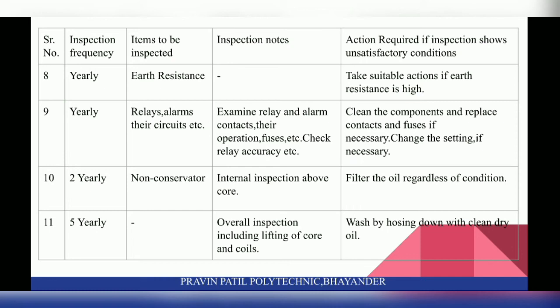On a two-yearly basis, check the non-conservator with internal inspection above the core. Action required: Filter the oil regardless of condition. On a five-yearly basis, perform an overall inspection including lifting of the core and coils, and wash by hosing down with clean dry oil — remove the windings from the transformer and core and fill fresh oil in the transformer tank.